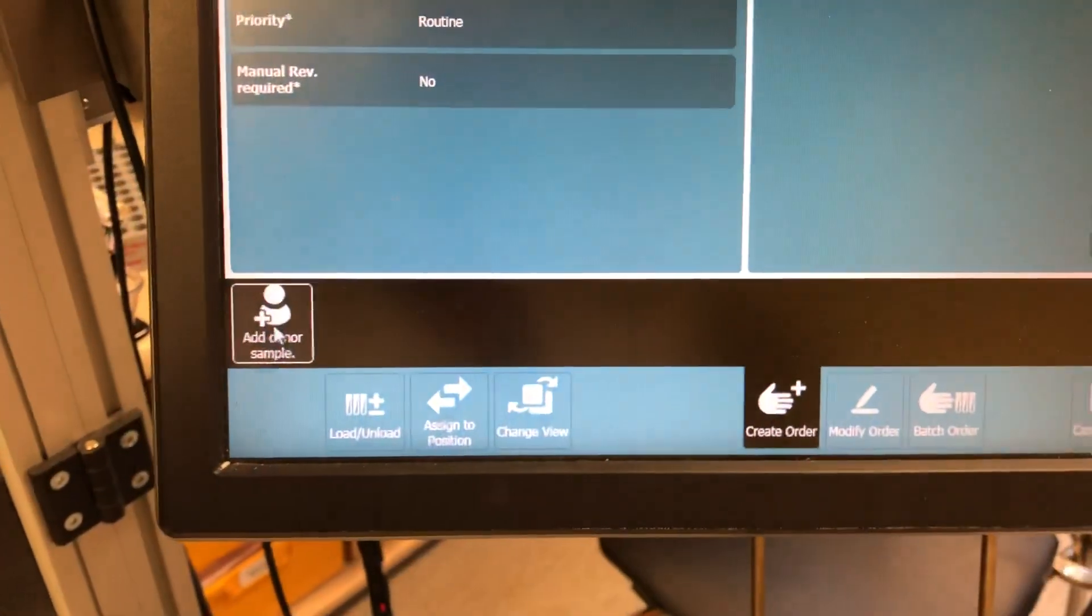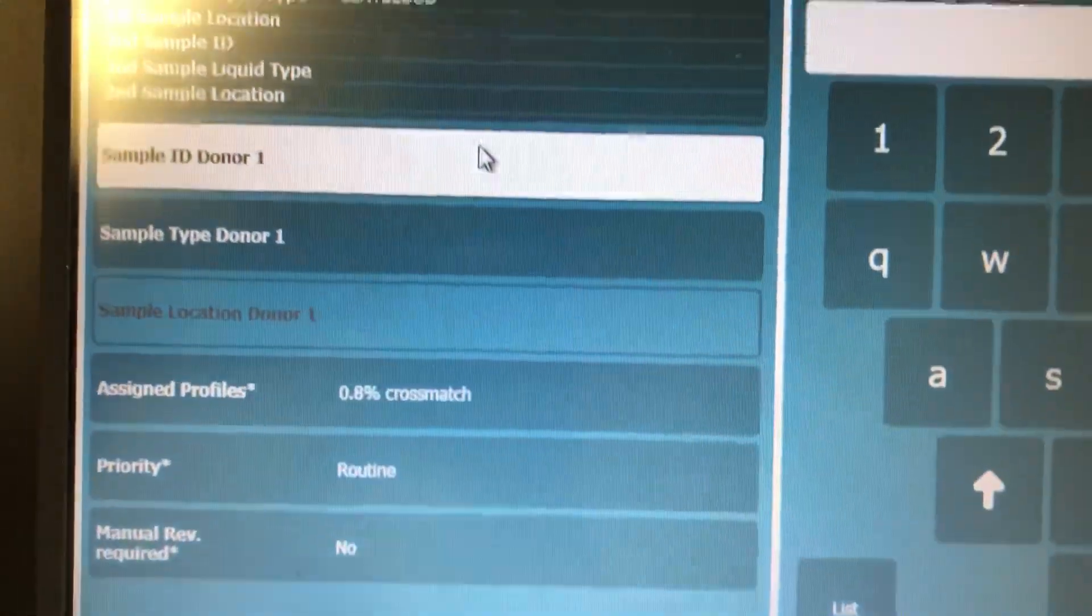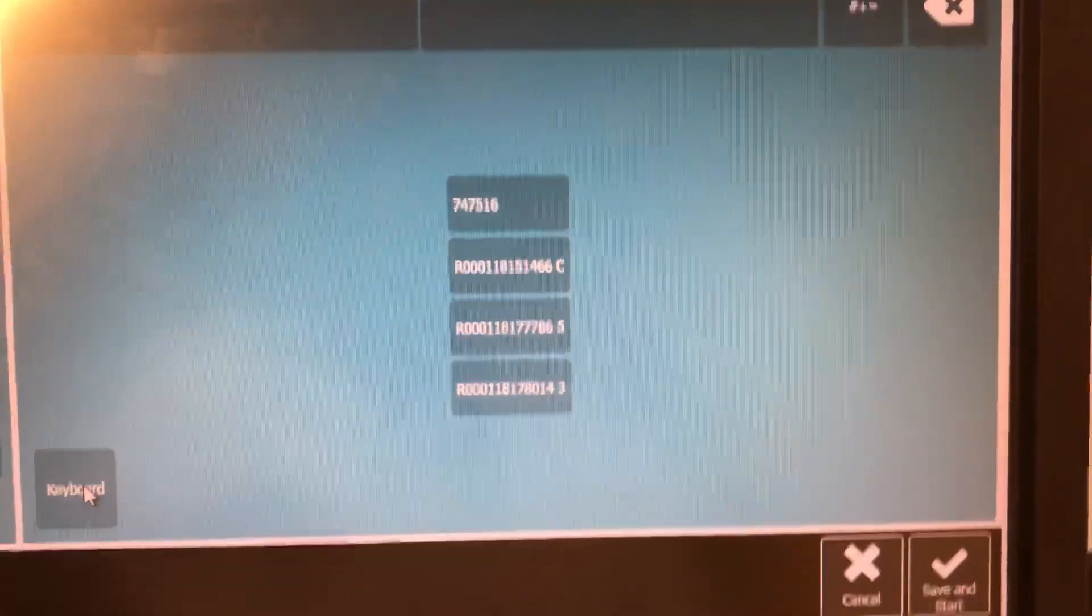So on the 0.8% cross match I click on add donor sample. Now I have to tell it which one it is so I go to sample ID donor 1. Now you'll see that nothing has filled in here in the sample ID field but you'll notice down here this list button has become active. So I hit list and it tells me everything that's on board the analyzer. So that's my primary sample, that's my donor sample 1, donor sample 2, and donor sample 3.